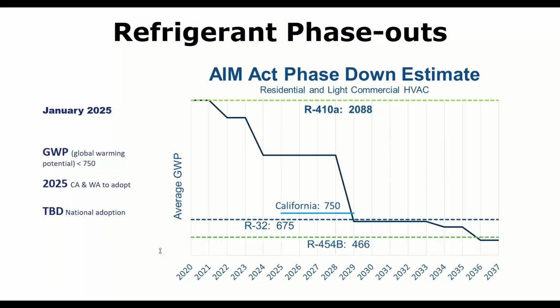The main driver of all this is the global warming potential limits instituted by certain states and/or federally. The big target is 750 maximum global warming potential. Some refrigerants will be able to handle that, some won't. R410A is up here at 2088, so it will not be permitted when these new metrics kick in.